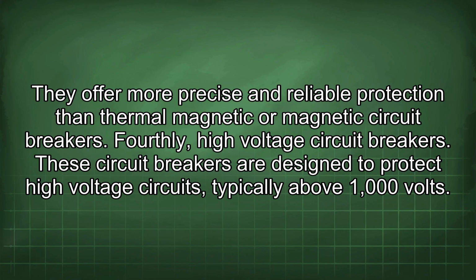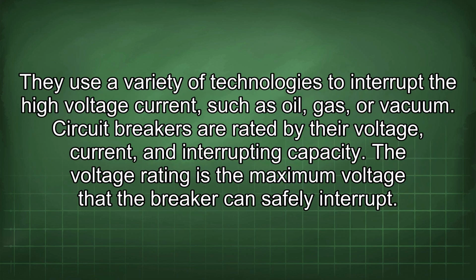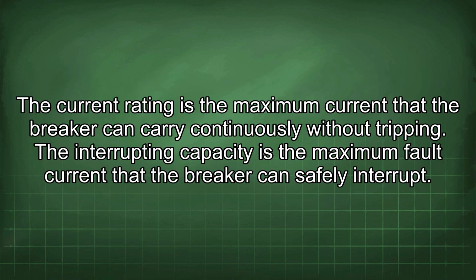Fourthly, high-voltage circuit breakers. These circuit breakers are designed to protect high-voltage circuits, typically above 1000 volts. They use a variety of technologies to interrupt the high-voltage current, such as oil, gas, or vacuum. Circuit breakers are rated by their voltage, current, and interrupting capacity. The voltage rating is the maximum voltage that the breaker can safely interrupt. The current rating is the maximum current that the breaker can carry continuously without tripping. The interrupting capacity is the maximum fault current that the breaker can safely interrupt.